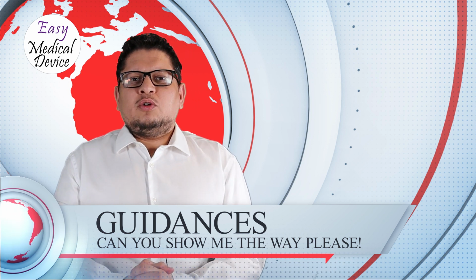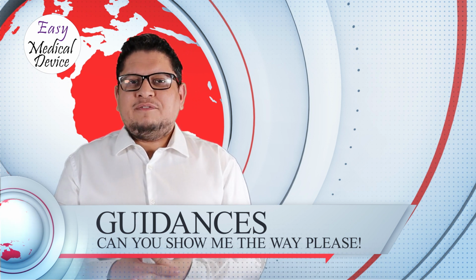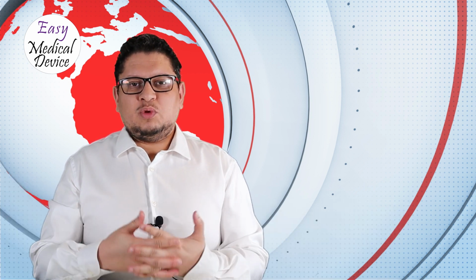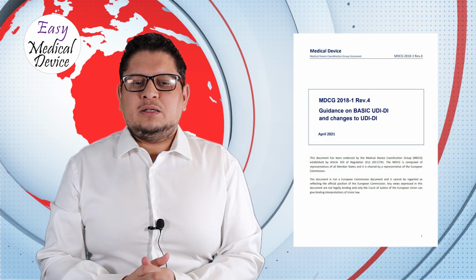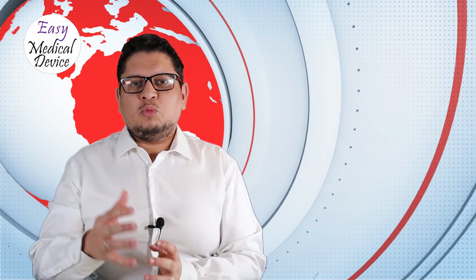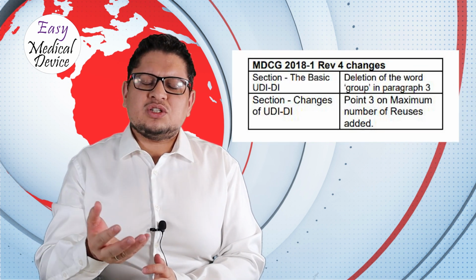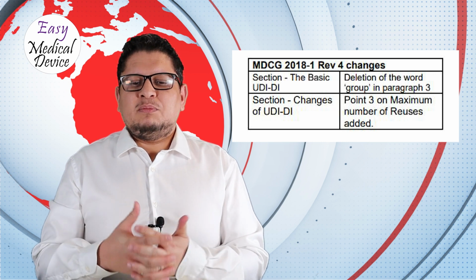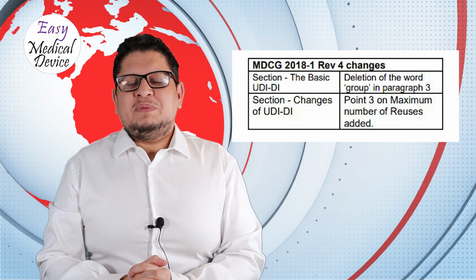Okay, so now we are going to the guidance and standards. So we have some new guidances that were published, but we have also some guidances that were just updated. So we have the MDCG 2018-1, which is the guidance on UDI and basic UDI-DI that was updated. So there were 2 elements that were changed. There was a paragraph where 1 word was removed, but there was also an addition of 1 paragraph, which is a paragraph related to the maximum number of reuse of medical device.